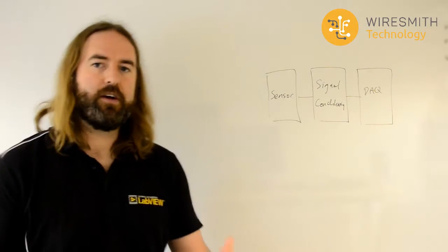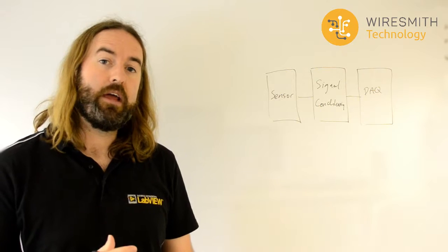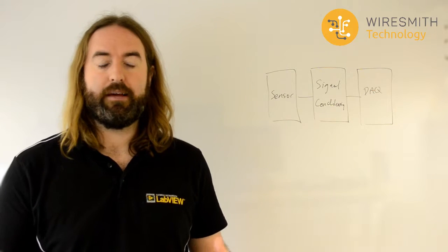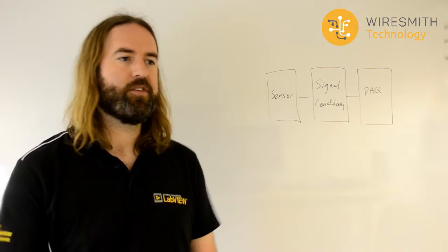And that has a few advantages, the big one being that now you can do this on your own schedule, you know what the process is that's been gone through, and that can avoid having to send hardware off for recalibration constantly. Now this means that when there's any questions about the results, you can go back and repeat this process as well and say, no, look, we know the sensor's good, we know the data acquisition's good.